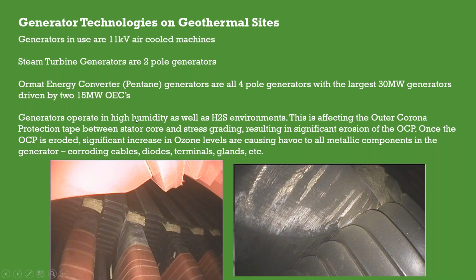Generators operate in a high humidity as well as H2S environment. It always rains in New Zealand, so the humidity is a natural part of that. But in these geothermal sites, there's a lot of hydrogen sulfide. So this directly affects some components in the generators. On rotor coils, if your rotor coils are not silver plated or tinned or painted, you immediately see the corrosion.